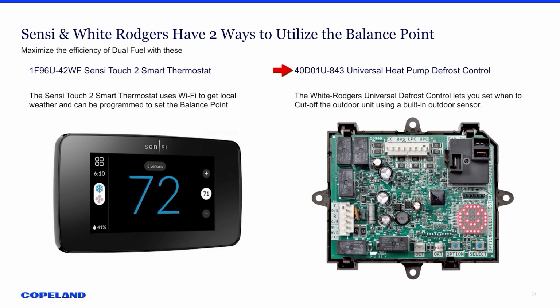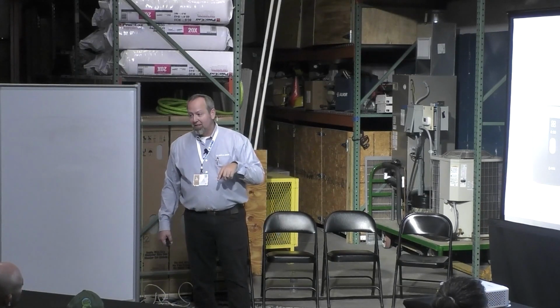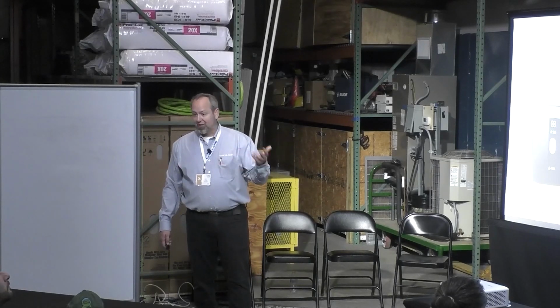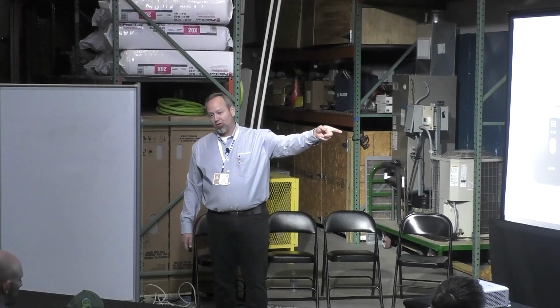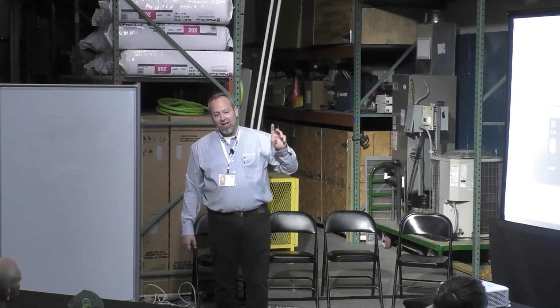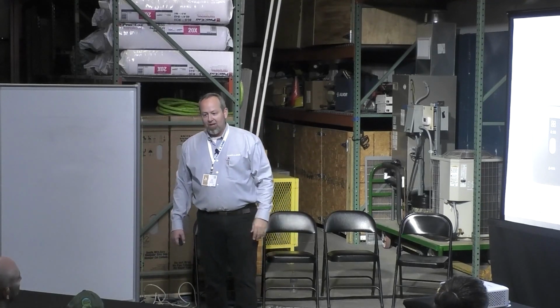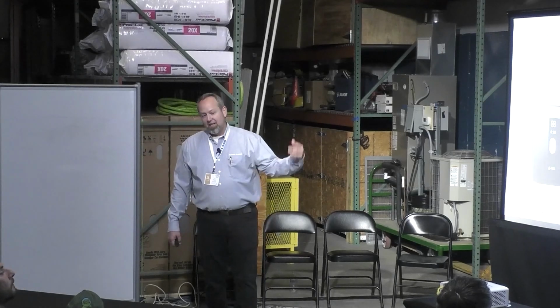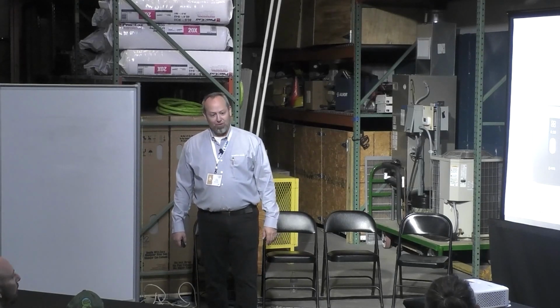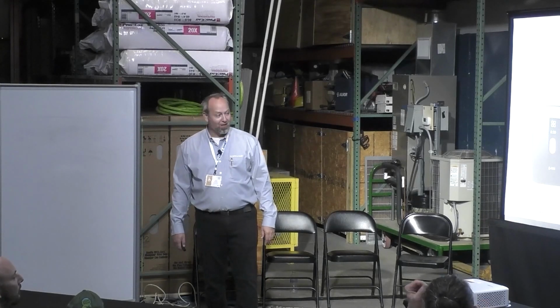The 40D 01U, our universal defrost board, has a couple of plugs for that. One, it has the option of demand or time defrost. So if you're out on a heat pump that has a time defrost in it, and the homeowner's getting a defrost every 30 minutes, you have the ability to upgrade that board to our defrost board and program it to go demand, so that they're not going into defrost every half an hour and wasting all that energy. And the upgrade to that board will cover itself in the homeowner's savings in short order.